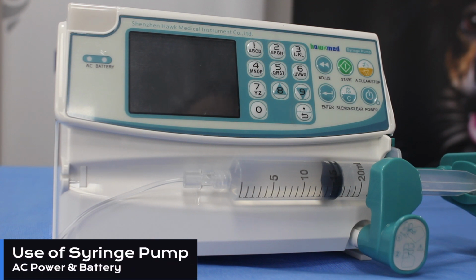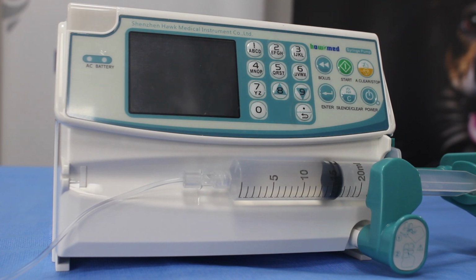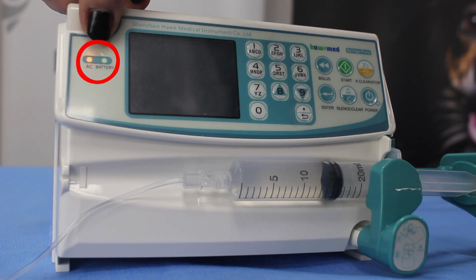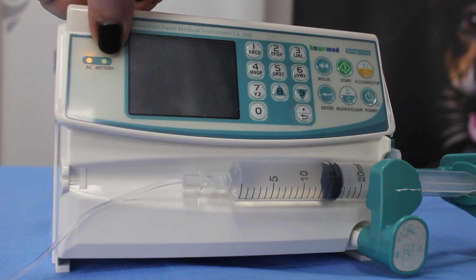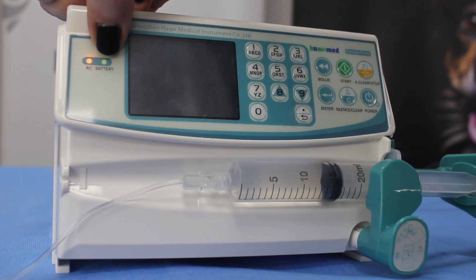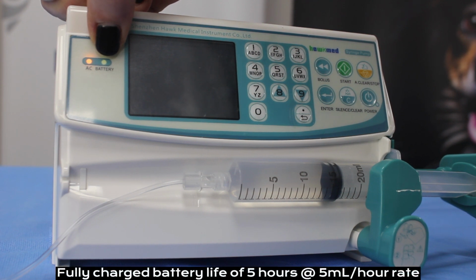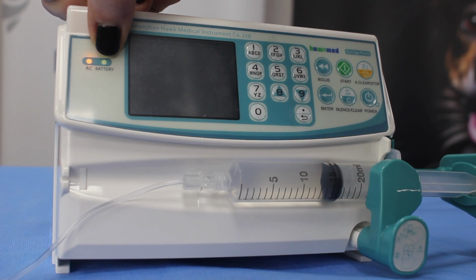To operate our syringe pump, we can first supply power via the power cord and switching on at the wall. We can see that the AC light has illuminated and the green light next to it above battery is also illuminated. When the battery light is illuminated green, this indicates that the power supply is charging the internal battery. Once this light turns off, it shows that the battery has a full charge and means that the syringe pump can be used while no longer plugged in to the power supply.